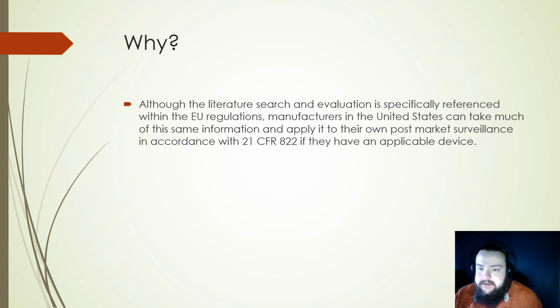So, in the context of this discussion, most of what I've been talking about has been in reference to development and maintenance of your clinical evaluation report, which would be a European regulation. However, if you look to the United States in Title 21, the Code of Federal Regulations, Part 822, if you have an applicable device, you can use everything we talked about for the post-market surveillance of your device within the United States as well. So even though it's been in the context of your clinical evaluation report, you can do these same activities as part of your post-market surveillance.